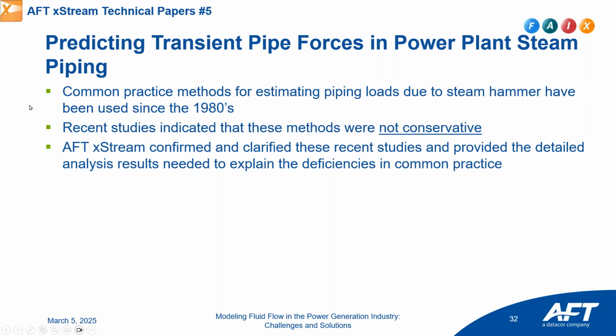Predicting transient pipe forces in power plant steam piping is what the papers are really about. Common practice methods for estimating piping loads due to steam hammer have been used since the 1980s. Some recent studies that came out starting about 10 years or so ago by other companies were indicating that these methods were not conservative. They were not able to really explain why, but they were calling into question some of these methods that have been used. And these are methods used on forces in steam piping that are used to assess what type of pipe supports are needed. These methods have been used, you can look in the literature, in the design of a lot of nuclear power plants.